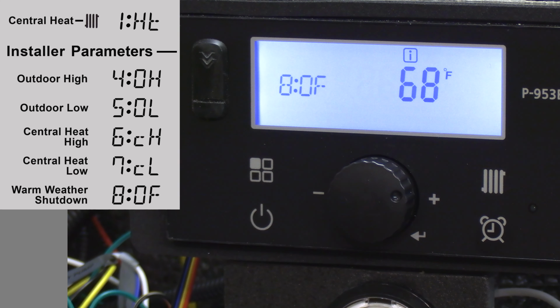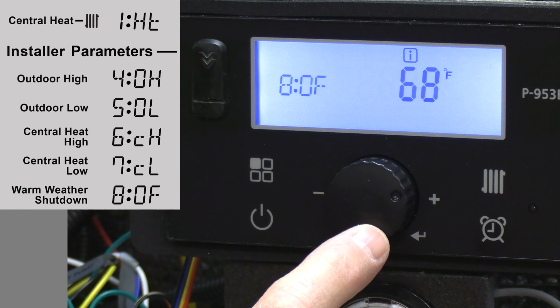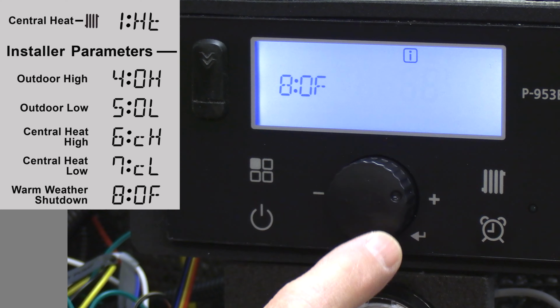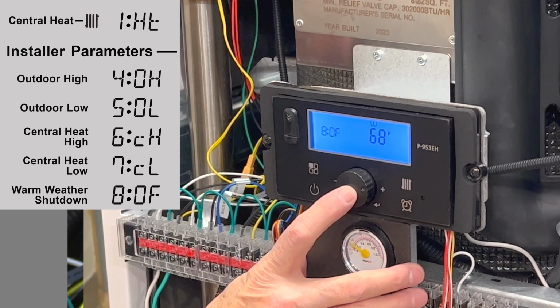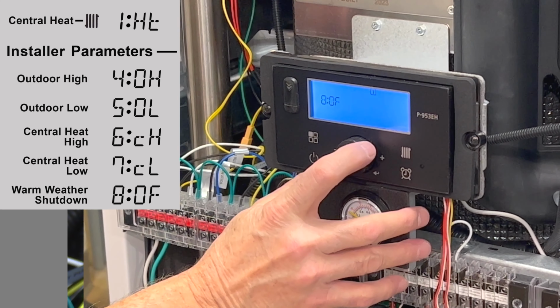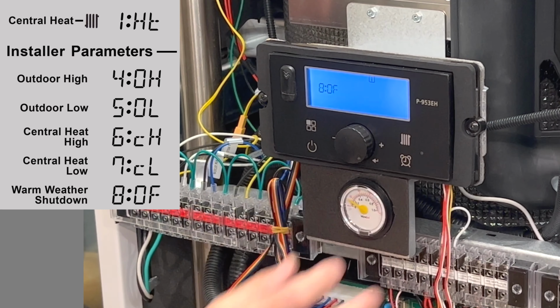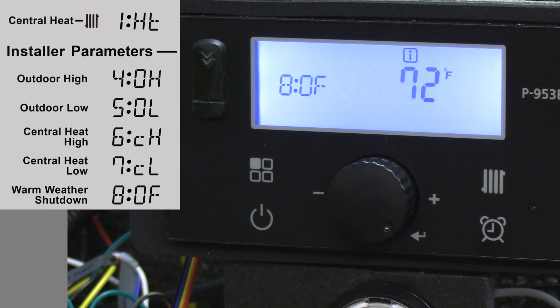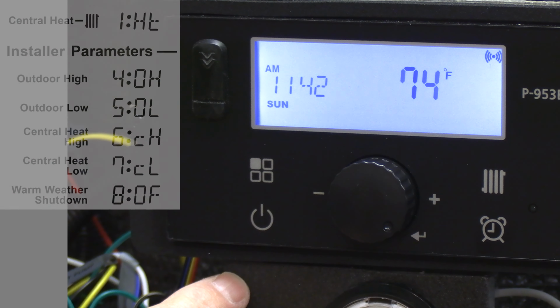So maybe it's an elderly housing project, and sometimes they want the heat on at 70 or 72. Again, to make that adjustment, hit the scroll select till it's flashing, and now in this example I'll bring that to 72 degrees. Press that scroll select again, and now I've stored it. So here we've adjusted our outdoor reset curve. Very simply, now that we've stored it, you can come back, just hit the power button, and we're back to normal operation.